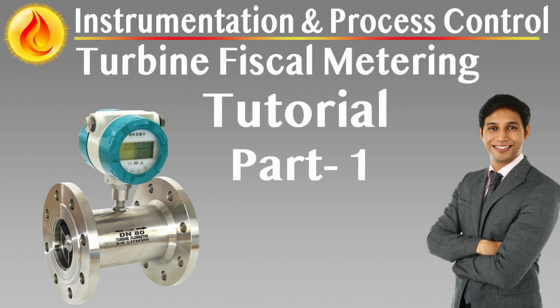Internal coating and integrity assurance. The internal surface of the prover must have a uniform bore with a non-porous, chemically resistant coating. The coating must resist explosive decompression and retain integrity across the full design temperature and pressure range. All surface preparation, application, and repair procedures must be documented and approved. The coating ensures that sphere travel is consistent and not affected by friction variations or degradation over time.